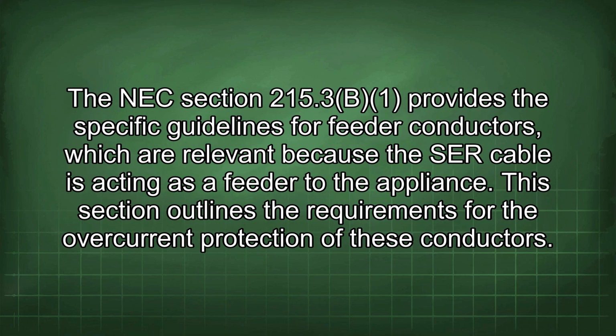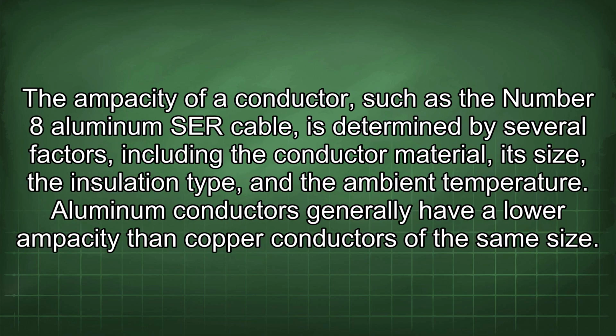The NEC Section 215.3 provides the specific guidelines for feeder conductors, which are relevant because the SER cable is acting as a feeder to the appliance. This section outlines the requirements for the overcurrent protection of these conductors. The ampacity of a conductor, such as the number 8 aluminum SER cable, is determined by several factors, including the conductor material, its size, the insulation type, and the ambient temperature.